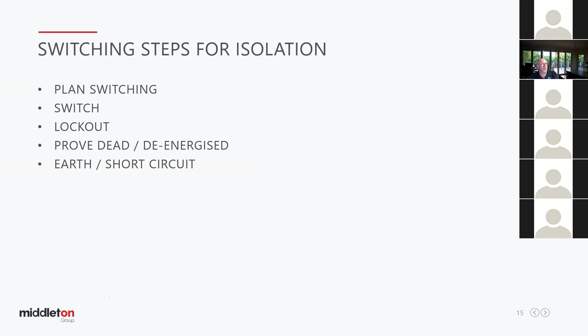So earthing. Here's a basic setup for an earthed section of line. So here's where we want to work. We've got some people actually applying earths. Well, look at this at the moment. Quick comment about earths. You've got your isolation point here locked out. It is most usual to apply a main earth at that point, that potential point of infeed. Another main earth if there's another potential point of infeed. And then close to the work site, as close as possible, there's usually working earths or local earths. Sometimes the main earths are called primary earths, and sometimes the working earths are called secondary earths. There's also other names for them, but I'll stick with those for the moment.